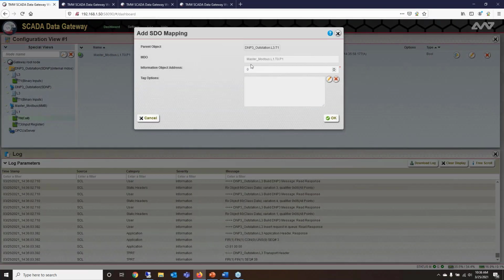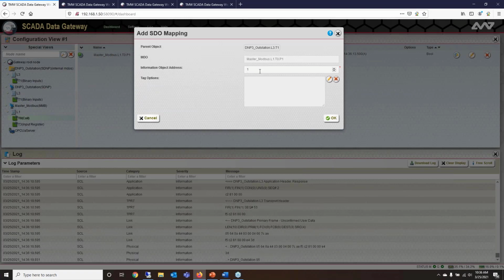At that point, you'll get a pop-up telling you exactly where you're going to put it. To keep things the same, I'm going to change my indexing to 1, so that 0.1 inside my Modbus is 0.1 inside my DNP database. This could be organized however you want, it doesn't necessarily have to be this way. If your downstream devices don't line up with your control center, you can wire this however you want, but for me it makes most logical sense to keep these indexes the same.